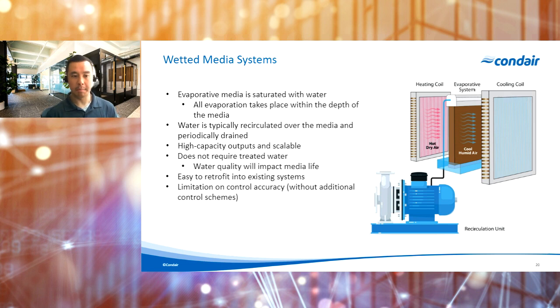Now, one of the main benefits to using an evaporative media system over some of the other technologies that we'll talk about is that a media system can operate on most water qualities. So unlike atomizing systems or ultrasonic units, systems that we'll talk about, those systems do require treated water, so either reverse osmosis or deionized. But with wetted media systems, we are a bit more flexible in terms of the type of water that we can put over the media.